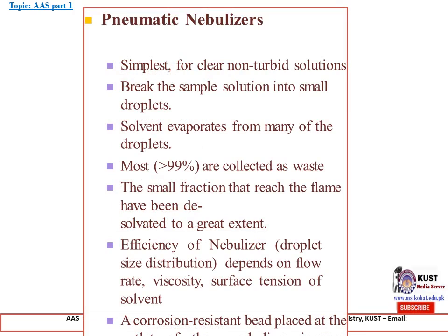Now, pneumatic nebulizer is a type of nebulization. What is the function of a pneumatic nebulizer? A pneumatic nebulizer is simplest for clear, non-turbid solutions. It breaks the sample solution into small droplets. The solvent evaporates from many of the droplets. Most, greater than 99%, are collected as waste. The small fraction that reaches the flame have been de-solvated to a great extent.